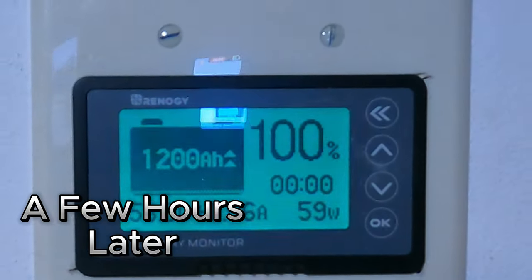It's about 2:30 today, and as you can see, the batteries are completely charged — they've been charged ever since 12:30, 1 o'clock. So from last night, the mini split ran all night long — we left it on all night just to show you what it would drop down to. As of right now we're fully charged back to 1,200 amp hours, 100% charge on the batteries. We have over 60 kilowatt hours of storage in our batteries and 1,200 amp hours of storage.